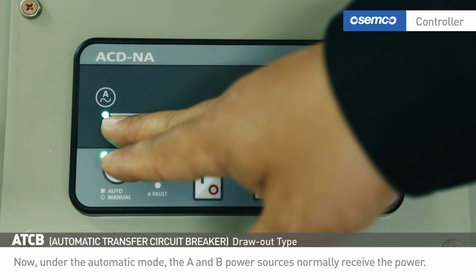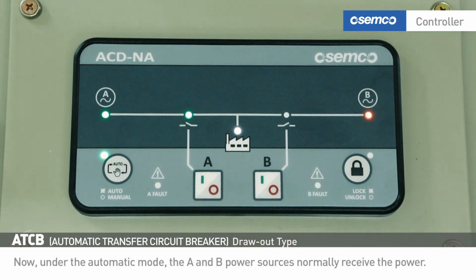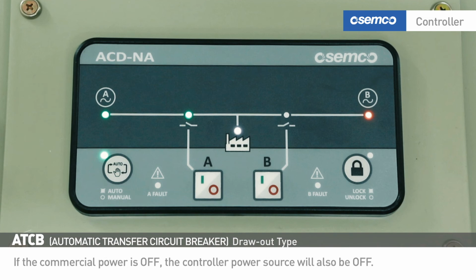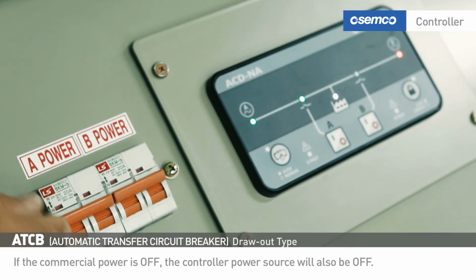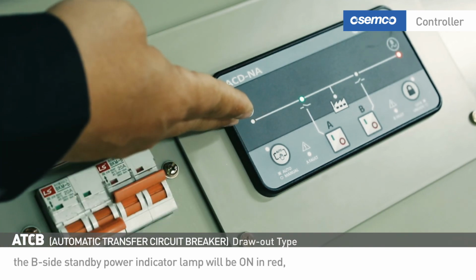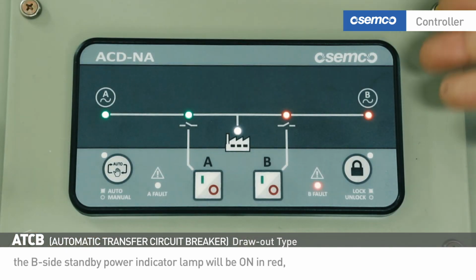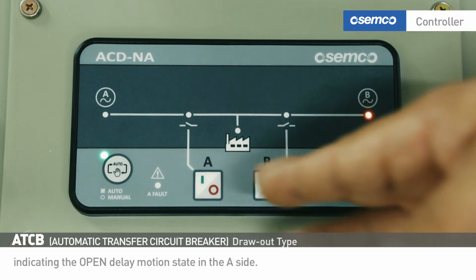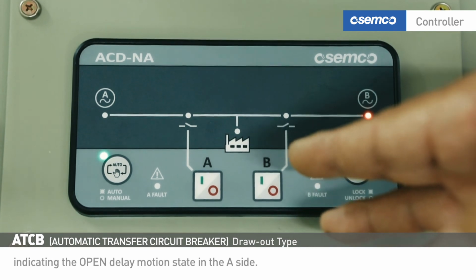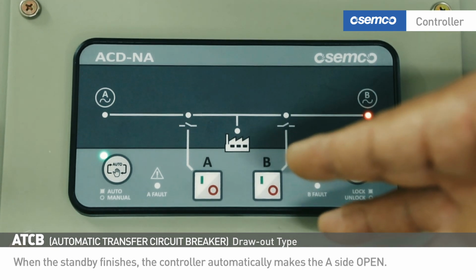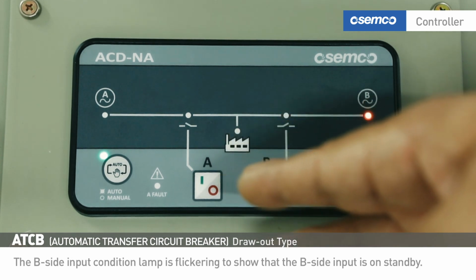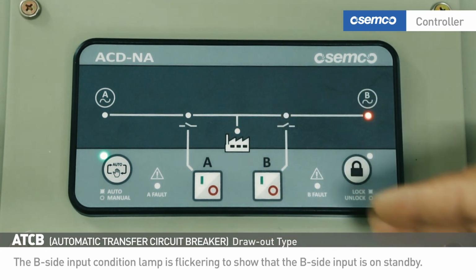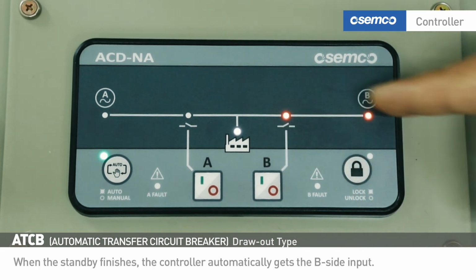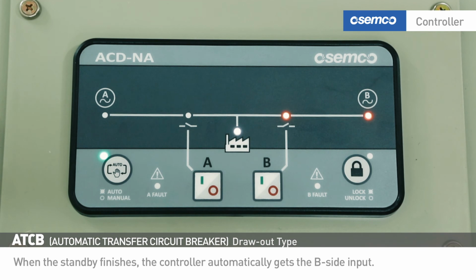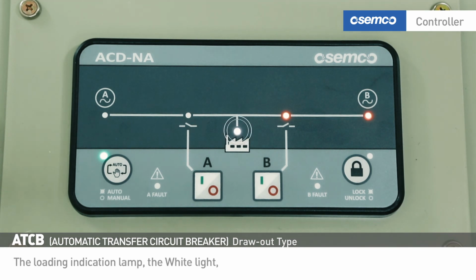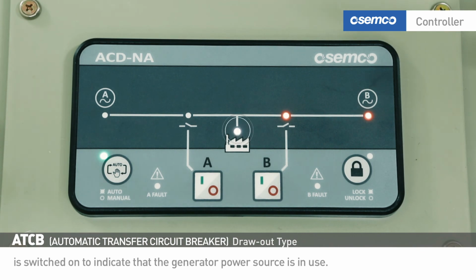Now, under the automatic mode, the A and B power sources normally receive the power. If the commercial power is off, the controller power source will also be off. If standby power is received in this state, the B-side standby power indicator lamp will be on in red, indicating the open delay motion state in the A side. When the standby finishes, the controller automatically makes the A side open. The B-side input condition lamp is flickering to show that the B-side input is on standby. When the standby finishes, the controller automatically gets the B-side input. The loading indication lamp, the white light, is switched on to indicate that the generator power source is in use.